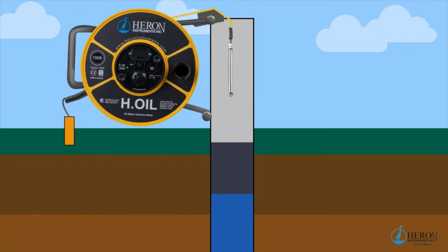When looking for the thickness of floating product, meaning LNAPL, lower the probe into the well until the top of the product is reached. Note, product is indicated by a solid tone. Water is indicated by an intermittent tone. Do not try to measure the product interface at this stage. Allow the probe to pass through the product into the water below, indicated by the intermittent tone. Now slowly withdraw the probe until the tone changes from intermittent to solid.